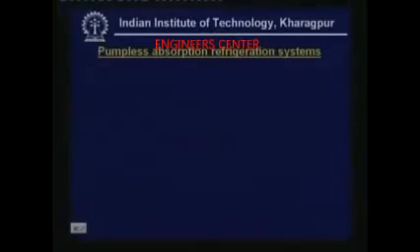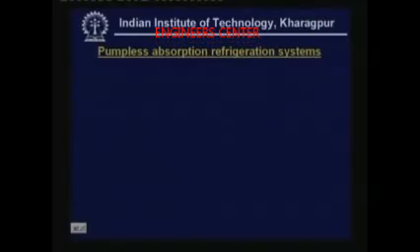The systems discussed so far - both water lithium bromide systems as well as ammonia water systems - are known as conventional absorption refrigeration systems. They do not run purely on heat because a certain amount of mechanical energy is also required to run the solution pump. So they are not purely heat-operated systems. You also have absorption systems known as pumpless absorption systems. As the name implies, a pumpless absorption refrigeration system does not have a pump.